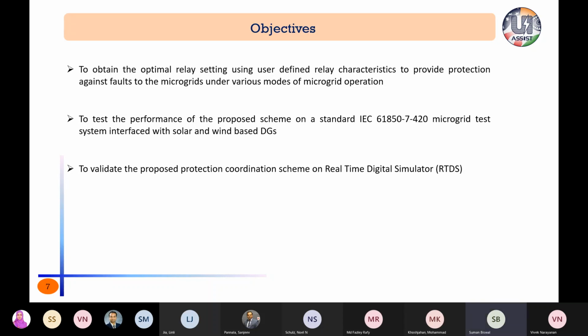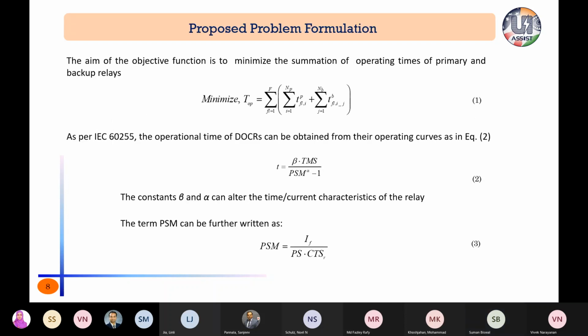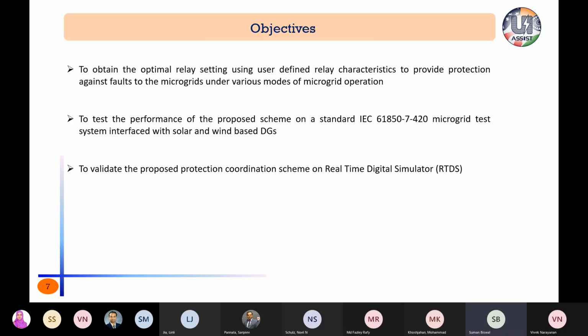As we have discussed, a particular setting will not take care of all other network topologies. So the settings need to be modified based on the scenario. Also, we'll test the system on the microgrid test bench, that is on IEC 61850, and later we'll see the validation procedure on the RTDS simulator. Actually, currently the validation is going on. It has not fulfilled the third objective, but I am currently working on the third objective.